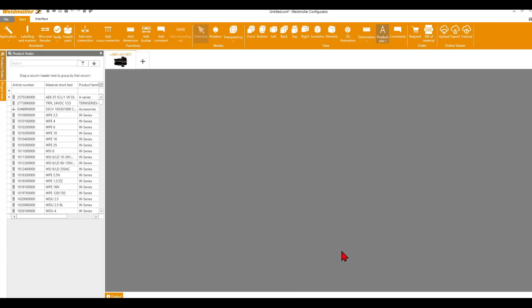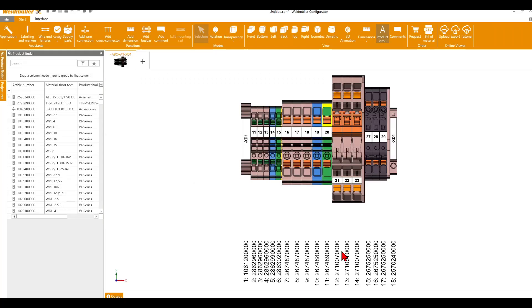And then comes the nice feature: we can click on Finish and Autosolve. What happens now is the Weidmüller Configurator checks your terminal strip for missing parts or anything incorrect, and then it autosolved these problems. Here you can now see that we get some end brackets and also the end plates for our different terminals.